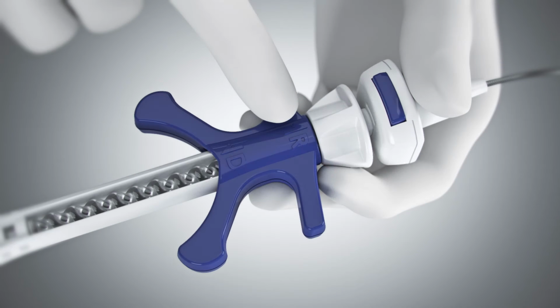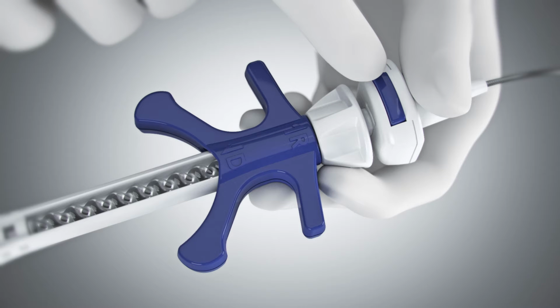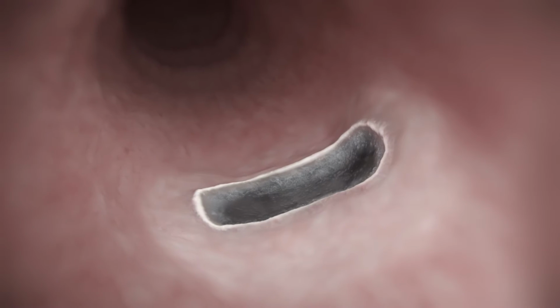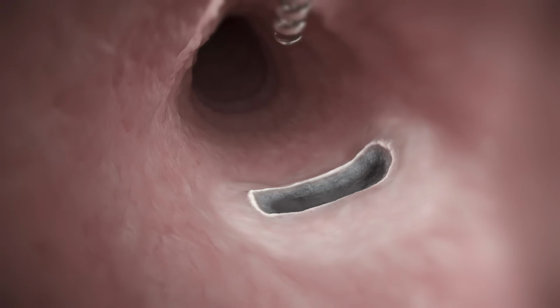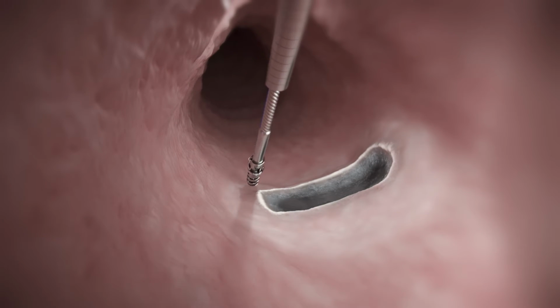Ensure the handle slider is in the reset position labeled R, and the push catheter is in the initial locked position. Maneuver the scope to the target site. Recommended helix tack placement is approximately 5 to 10 mm from the defect margin. Verify position before fully driving into tissue.